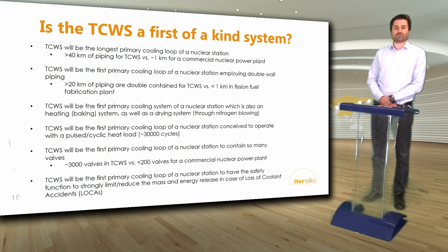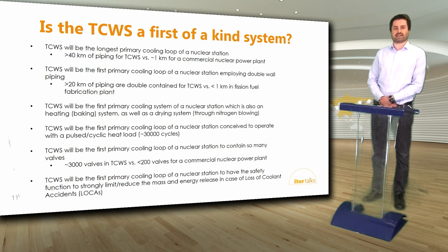The third very peculiar characteristic is that, in addition to being a water cooling system, it is also a baking and heating system. One of its main functions is to provide hot water and hot gas to clients in order to heat them up, thereby achieving optimal vacuum conditions inside the vacuum vessel. Another very peculiar characteristic is the huge number of valves — around 3,000 — which is at least one order of magnitude higher than the number of valves in fission power plants.